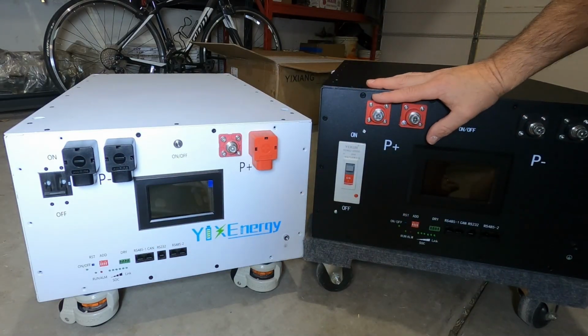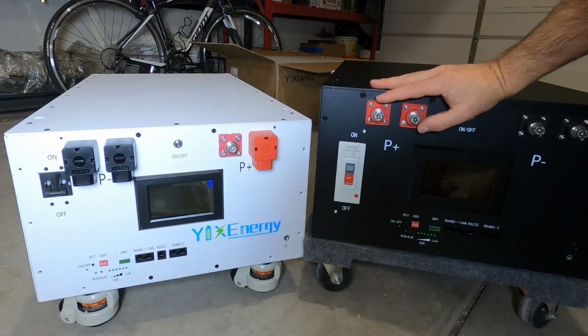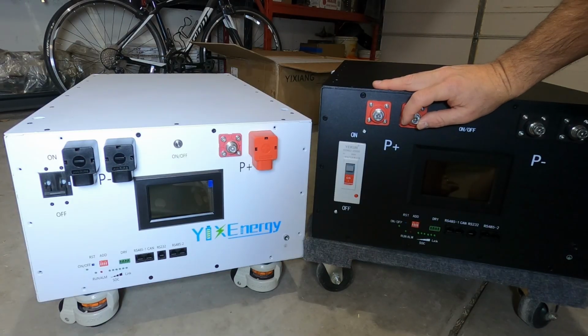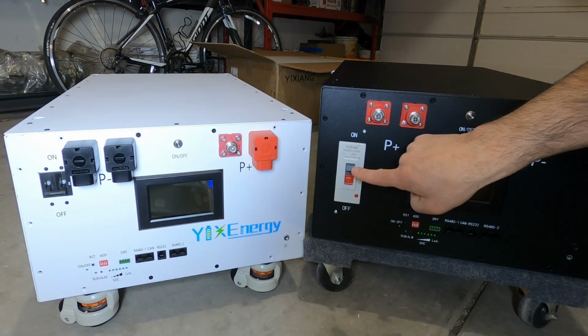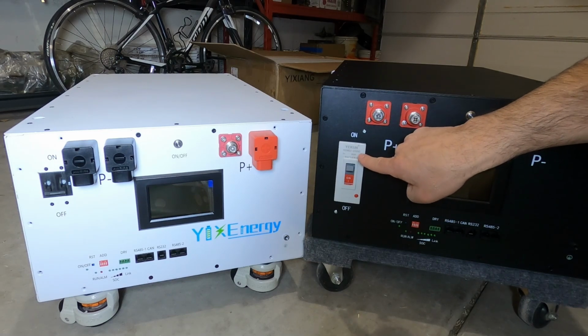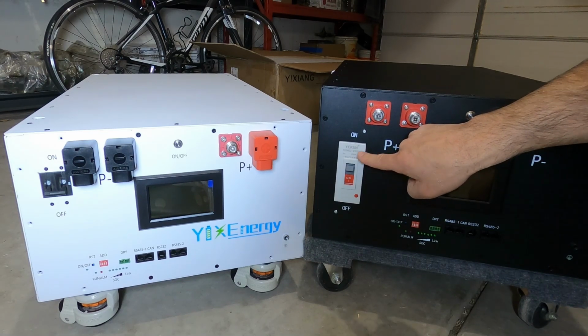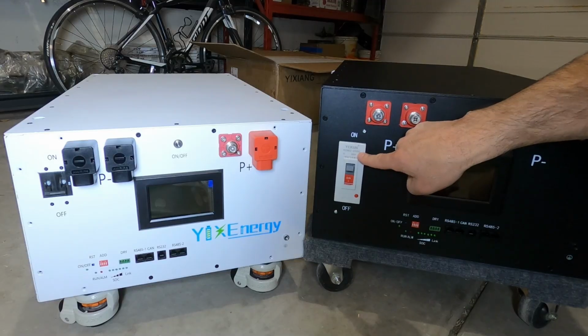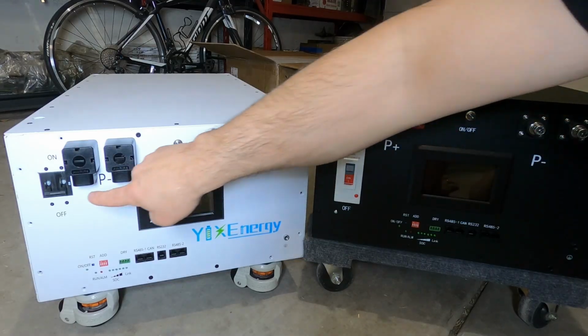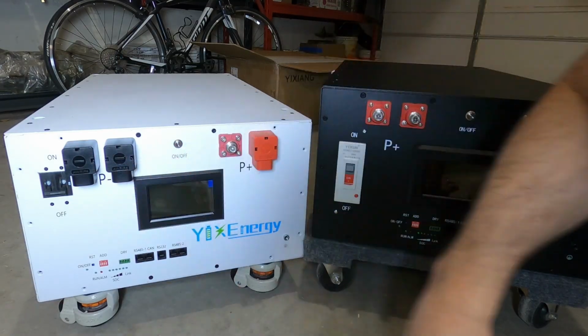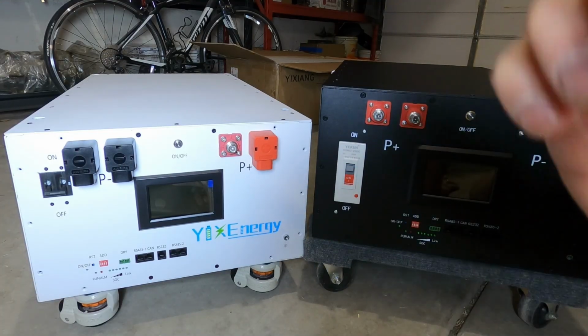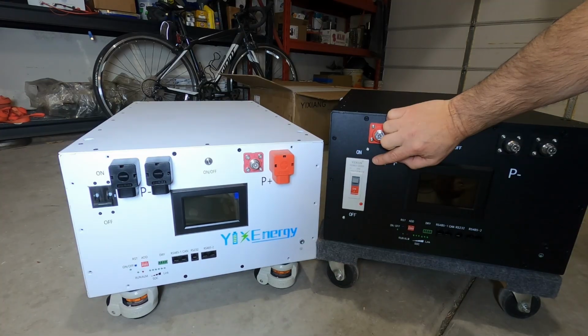We have a 200 amp BMS in these batteries. If you're pulling 200 amps, an 80% duty cycle on the breaker would need to be 250 amps rated, since 80% of 250 is 200 amps. Over here we have 220, so that's insufficient at 80% duty cycle. I will cover the bidirectional breaker a little bit further on in the video.